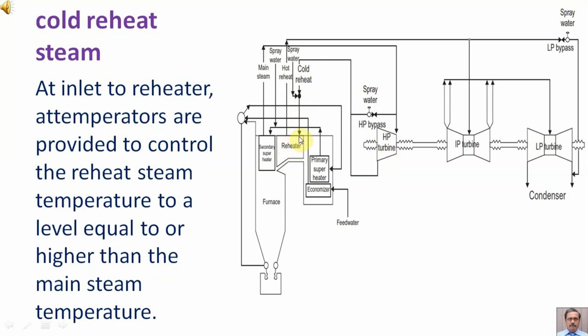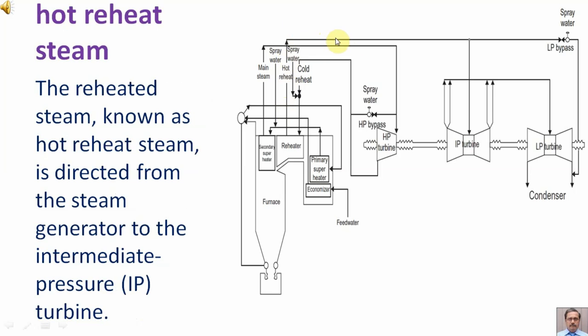At the inlet to the reheater, spray water is provided to control the reheat steam temperature to a level equal to or higher than the main steam temperature. The reheated steam, known as hot reheat steam, is directed from the steam generator to the intermediate pressure turbine.